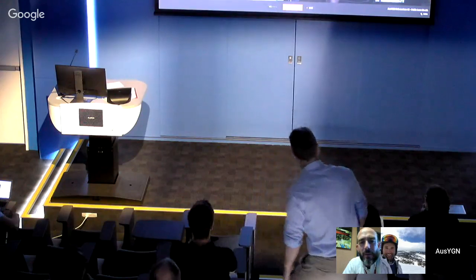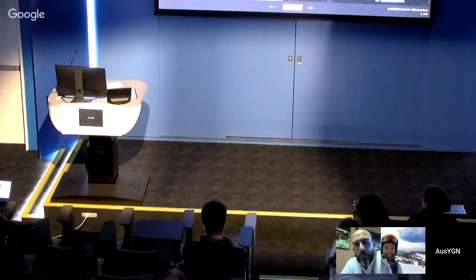Hi, Pablo. Thank you for your excellent presentations, and congratulations for the success. It's amazing, the work that you did, all the team in Argentina. My question is actually two questions, but one is about the internals of the steam generator. You mentioned that you found abrasion on the internals. Did you find corrosion as well, taking into account that the material is carbon steel? The second question, I put both questions in one and then leave to you the answer.